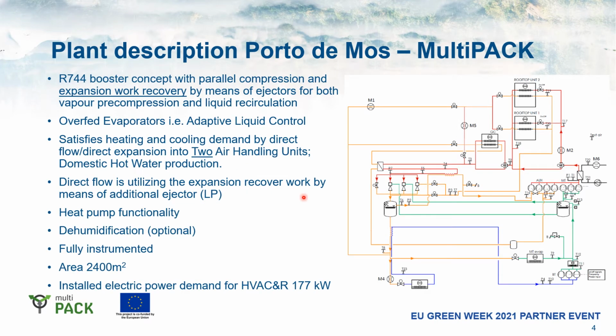Just to look at the plant side, what do we have in Porto de Mos, and what we call a MultiPACK? The MultiPACK is basically a CO2 booster concept with parallel compression and expansion work recovery by means of different ejectors. Here we have both high pressure lift ejectors, liquid ejectors, and low pressure lift ejectors, every one of them having a specific working task, which I come to later on. The system is able to run with overfed evaporators, as Danfoss is calling it, adaptive liquid control.